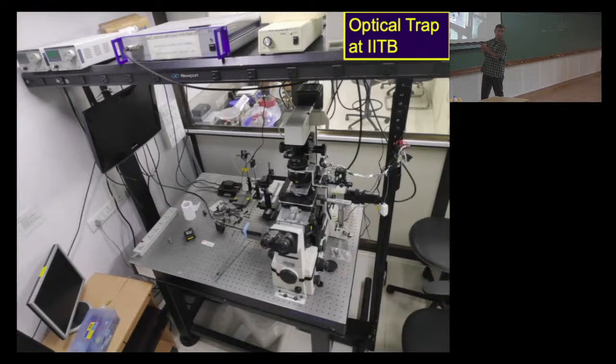That is where we keep the sample. Then that light beam continues upwards after passing through the object that you have trapped. It diverges, remember, right? Because it is passing through this objective lens, it focuses and then it diverges. And you will not see it, but there is a dichroic mirror inside this at a 45-degree angle. That dichroic mirror sends the light this way. There is another lens here which focuses that diverging beam and makes it a little less diverged. And then this light beam comes and hits this object here.